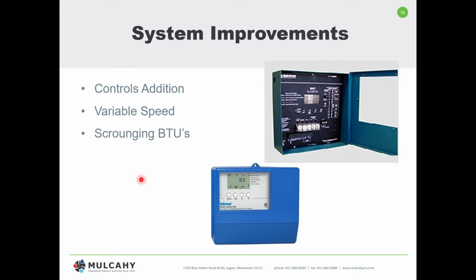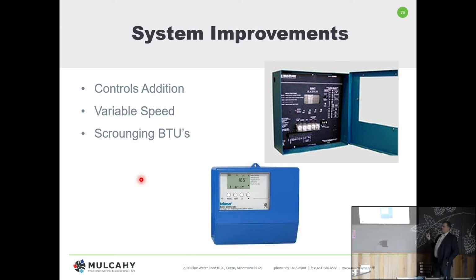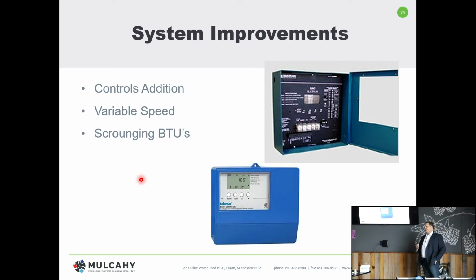What about something that said, well, geez, it's 30 degrees outside. I don't need 14 psi of steam. Let's only do 10. There's controls that'll do that. And if you want to interact with the building automation, we could sequence boilers. There's a lot of off-the-shelf controls that can make an old school system not perfect, but definitely better.